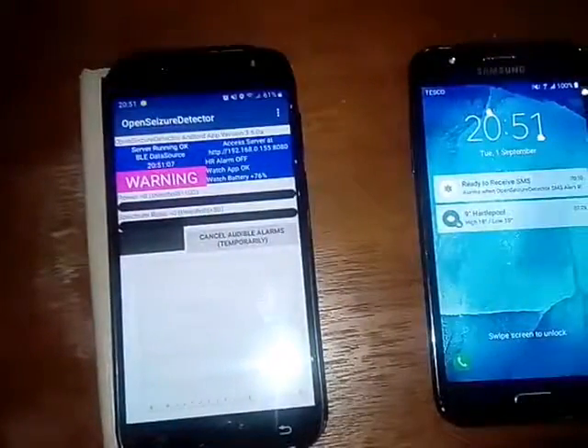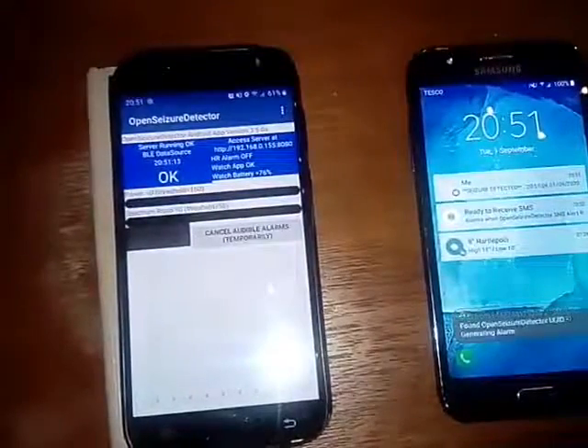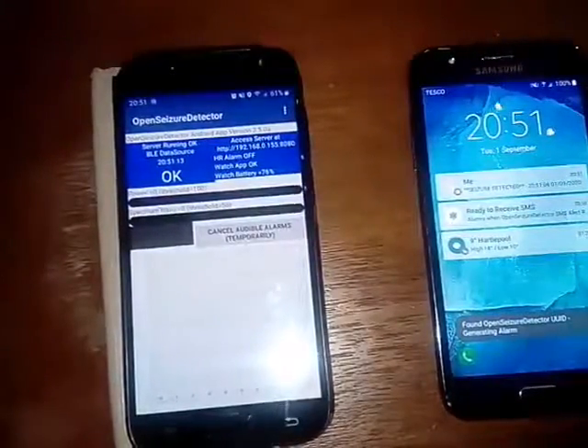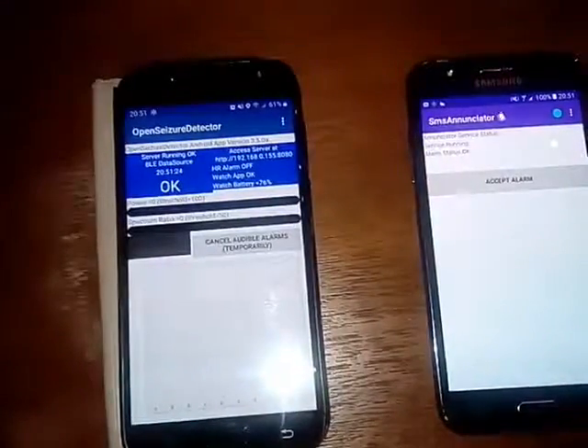We can see the SmsAnnunciator there — it was ready to receive, and there it's received it. Rather than just getting the ordinary beep for a text message, we're getting a rather aggressive noise. We can press accept alarm and that will quieten it down.